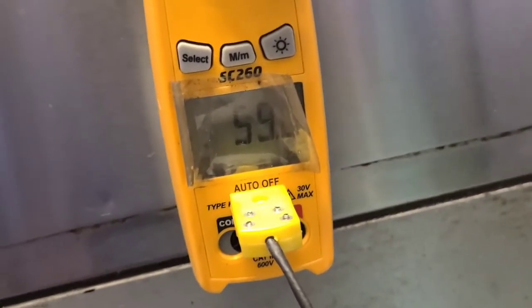I'm going to let it run, put my temperature probe in the unit, check the temperature, make sure it drops down. I'm going to keep an eye on it and let it run for a bit. Right now we're at 60 and the box is coming down.